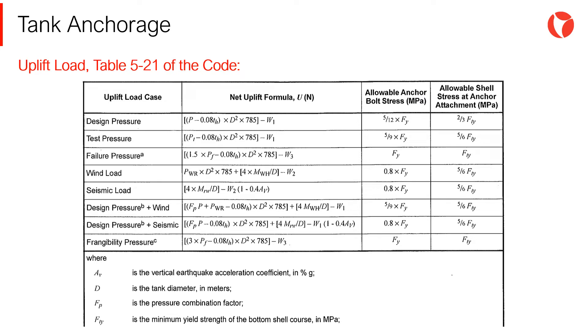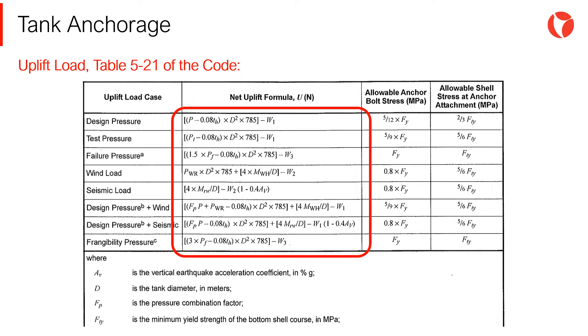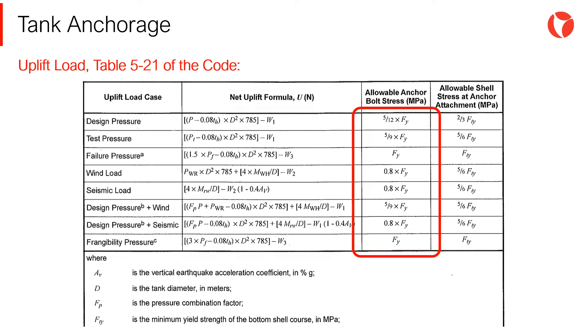The uplift load is calculated according to table 5-21 of the code, which is shown on the screen. Once the real load on each bolt is calculated, it is compared with the anchor bolt allowable stress obtained according to the table shown. This way the diameter and number of bolts preventing the tank from uplifting are selected.